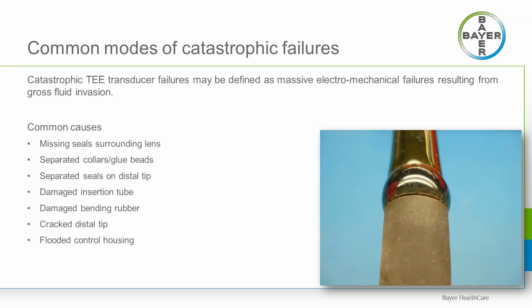Two common points of failure across all makes and models of TEE probes are separated collars and separated seals on the distal tip. The collars, or some people call them glue beads or adhesive beads, are a group of materials designed to adhere the bending rubber to the tip or to the tube, and are really designed to provide a watertight seal between these various components.